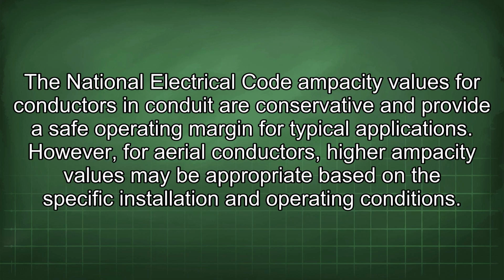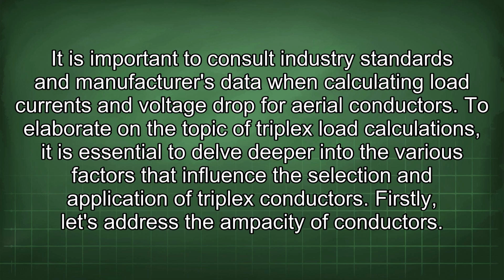The National Electrical Code ampacity values for conductors in conduit are conservative and provide a safe operating margin for typical applications. However, for aerial conductors, higher ampacity values may be appropriate based on the specific installation and operating conditions. It is important to consult industry standards and manufacturers' data when calculating load currents and voltage drop for aerial conductors. To elaborate on the topic of triplex load calculations, it is essential to delve deeper into the various factors that influence the selection and application of triplex conductors.